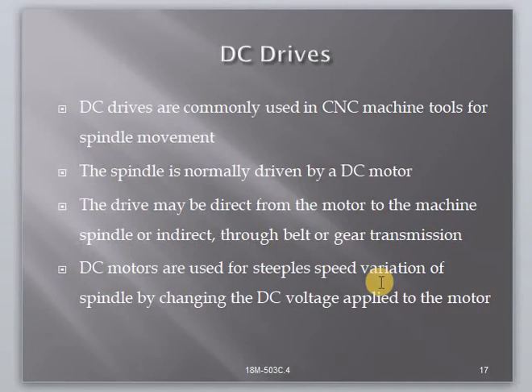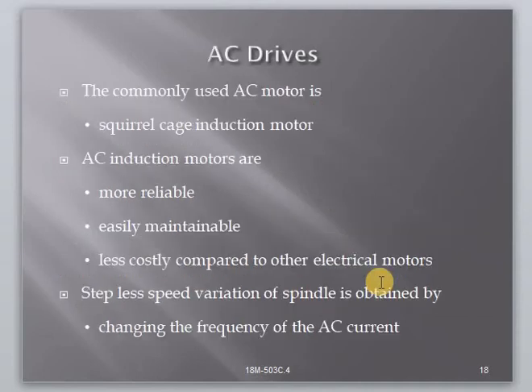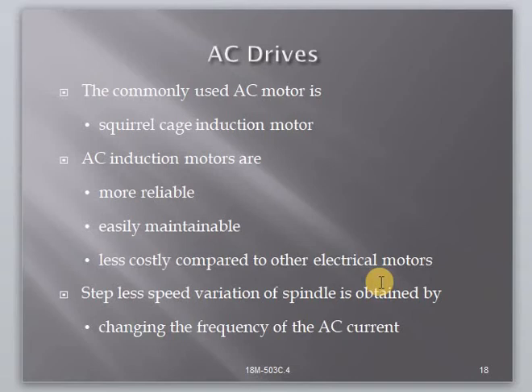In order to achieve the necessary dynamic behavior, the DC motor is operated in a closed loop system equipped with sensors to obtain velocity and position feedback signals. The AC servo motor has a rotor that is a permanent magnet while the stator is equipped with three-phase windings. The speed of the rotor equals the rotational frequency of the magnetic field of the stator, which is regulated by the frequency converter. AC motors are gradually replacing DC servo motors — the main reason being that there is no commutator or brushes in an AC servo motor, so maintenance is not much required. Furthermore, AC servos have a higher power-to-weight ratio and a faster response.